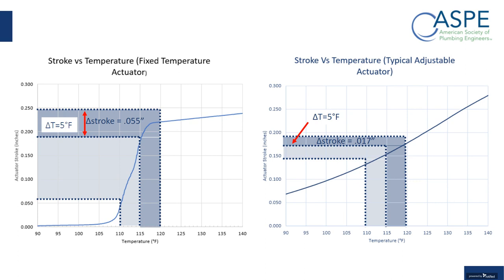So the result of that, there's two curves shown here. The one on the left is the fixed, and this curve is basically a temperature stroke curve. So you can see for different temperatures the distance that the actuator is stroking here. And then you can see it on the right for the adjustable. Because the adjustable is over a wide span, you need to have a wide operating range. So, if you look at the light gray and the dark gray in this diagram, this valve operates over a 10-degree span.